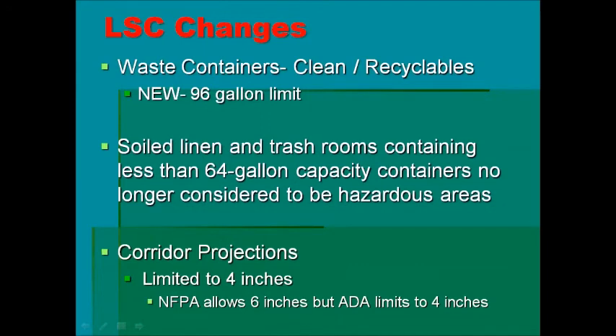When it comes to waste containers, both for clean or recyclable waste and soiled linens and utility trash, there have been some changes. For clean waste outside of a protected area, you can have containers up to 96 gallons - so if you've got a large recyclable container at your nurse's station under 96 gallons, it doesn't need to be in a protected room. For soiled utility or trash, the maximum in an unprotected area is 64 gallons.